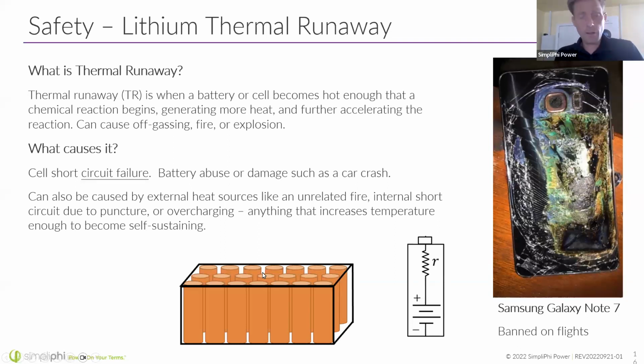If they develop too much pressure, they can off gas, and that means to release the electrolyte. It's like an organic solvent that allows lithium to move. If that electrolyte releases, it can catch on fire. And if that cell gets hot enough, maybe the middle cell catches on fire, it can heat up the cells around it. They can in turn off gas and heat up the cells around them. And that is known as thermal runaway. It's a chain reaction in which one cell heats the next cell, which off gases, which catches fire, which heats the next cell.